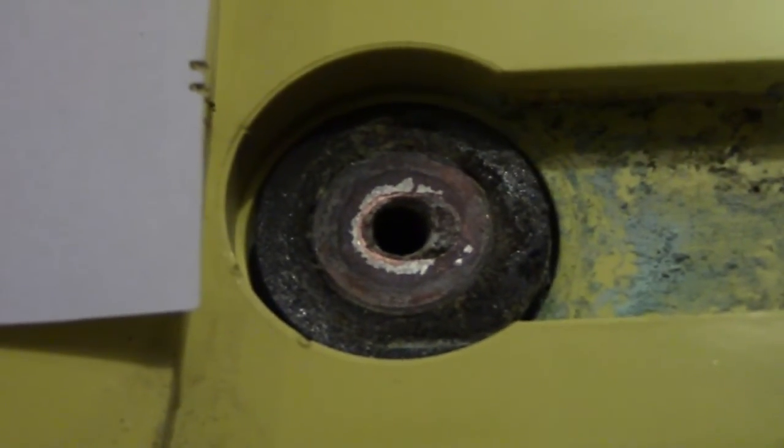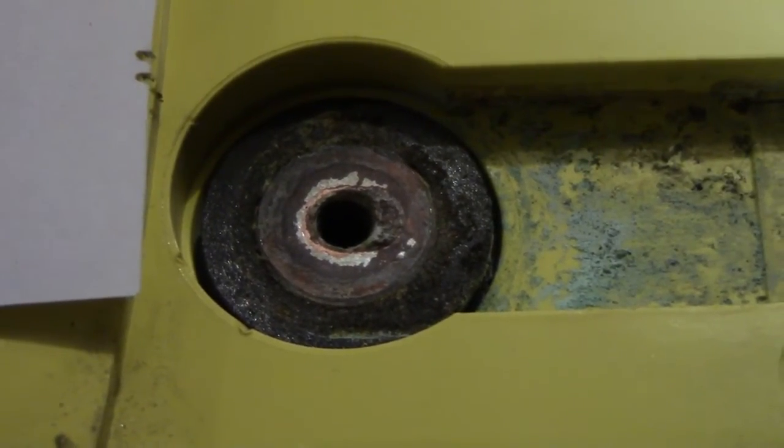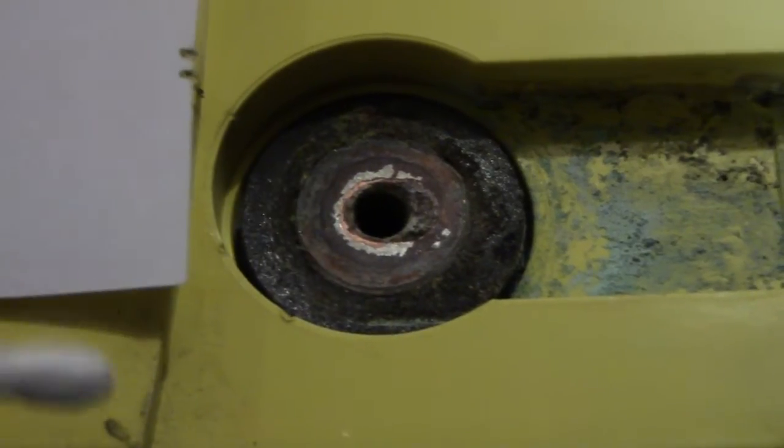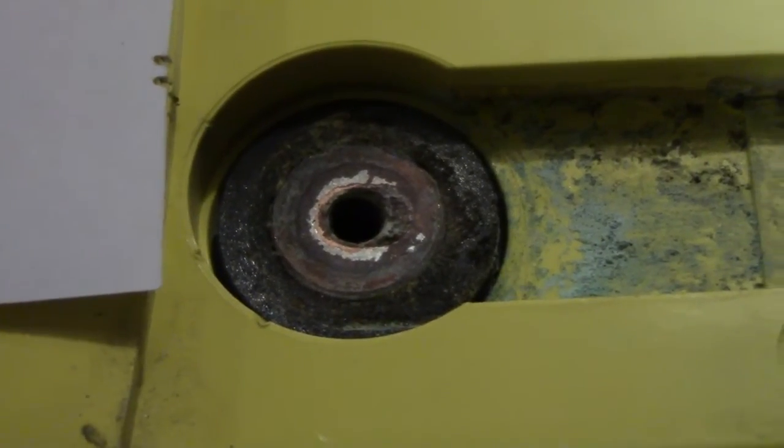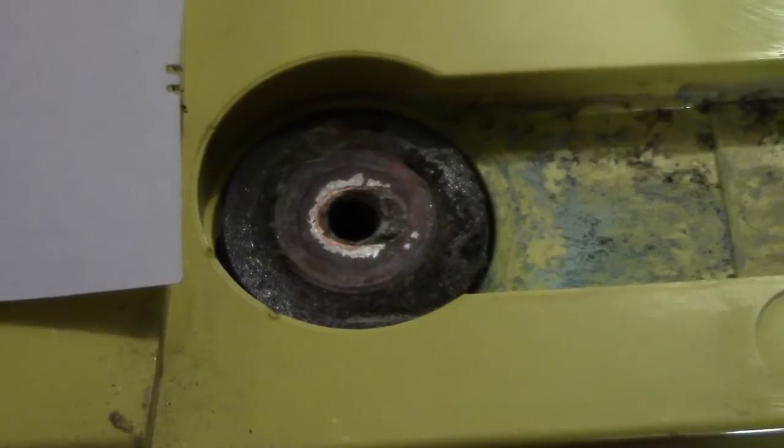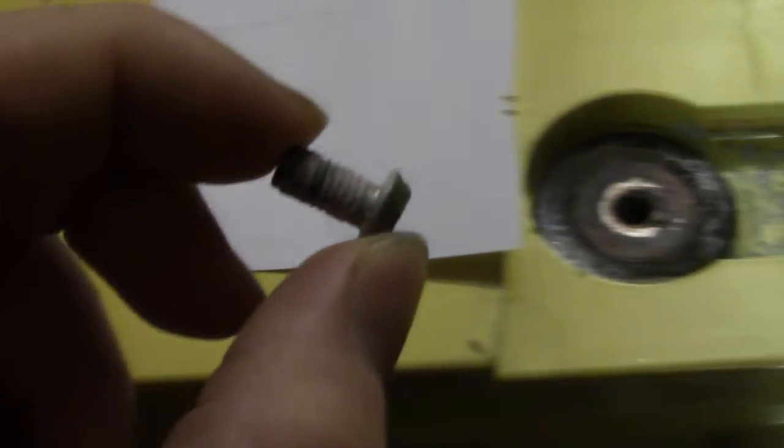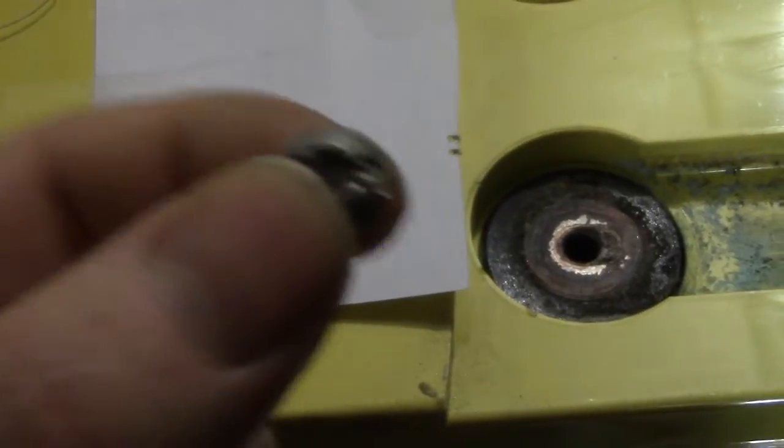The corrosion has gone beyond just the area around the terminal, but it has indeed corroded the terminal itself. All the conducting path we have left is this little piece of metal down there, which I'm sure can handle most of the current, but especially wouldn't be able to put anywhere near as much current as it was specified to do without overheating the terminal. So I've got to clean this stuff up properly, probably replace this screw, because it seems as if some stuff has gone down into the threads of it.